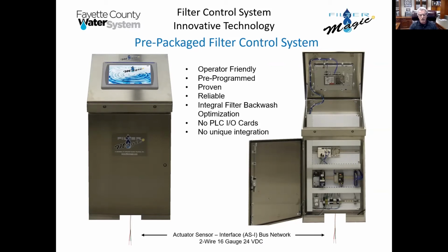Typically in a plant with 8 filters, we'd probably have 4 dual consoles. But that single console, or one more like it, could have handled the entire plant and eliminated all that conduit wire. Notice the PLC in the open door of the console has no I/O cards—our bus network eliminates all the I/O cards and hardware that can fail. It's not needed, which makes the panel emptier and troubleshooting that much easier. So we eliminate a lot of conduit wire and traditional hardware that just isn't needed.